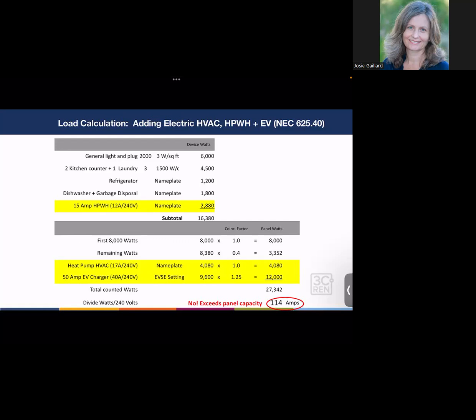And then we're going to try to put a big 50 amp car charger on there just to see what happens. And so this is the last yellow line. You can see 50 amp EV car charger with a nameplate rating of 40 amps. Again, 80% of the sort of title amps. So actually 40 amps at 240 volts. And that results in 9,600 device watts. The code tells us to apply a coincidence factor for this load of 1.25. EV chargers are often on for very long periods of time and can heat up wires. So, which is why that coincidence factor is kind of a multiplier higher than 1.